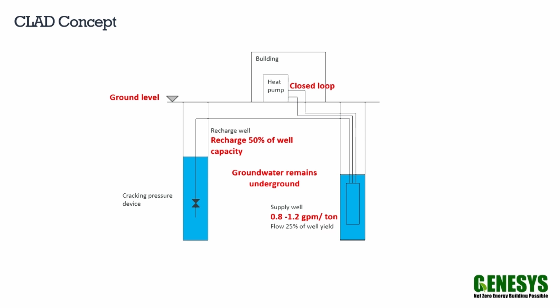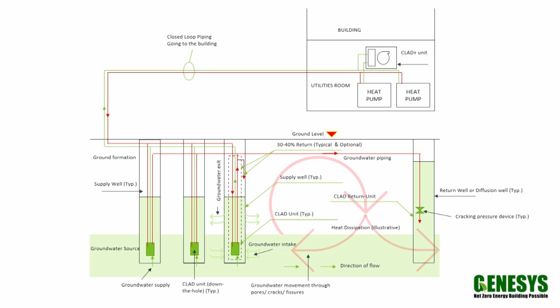The building side is still a closed loop system, so you can have antifreeze in it and it'll still run just fine. On the open loop side, you're pushing water in the direction of water flow, so you're not building up any thermal plume around the CLAD unit.